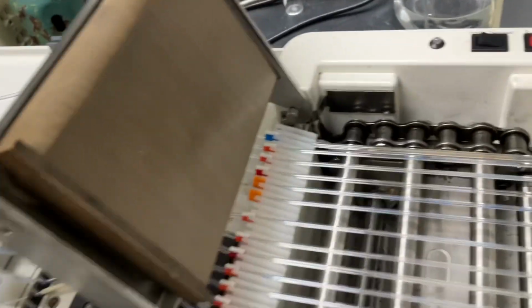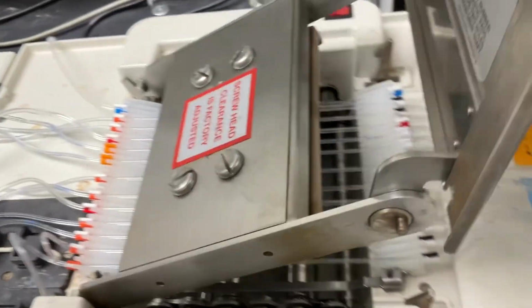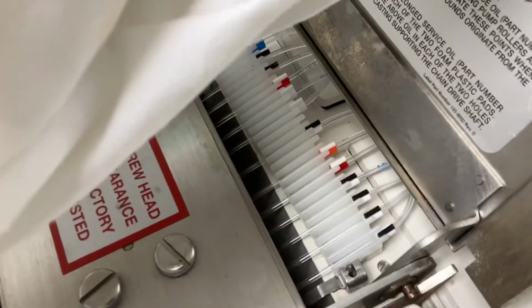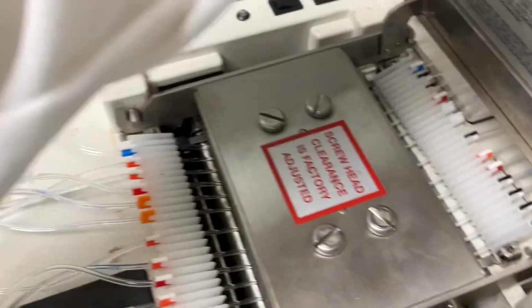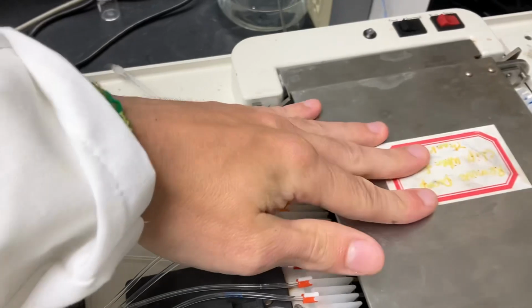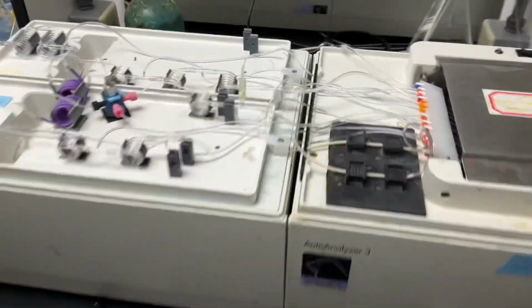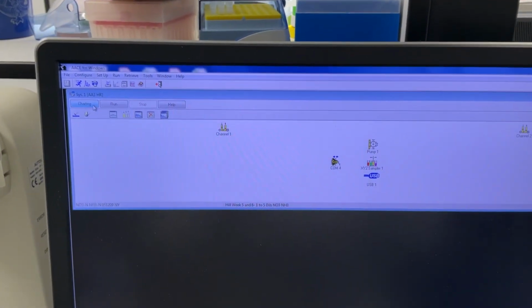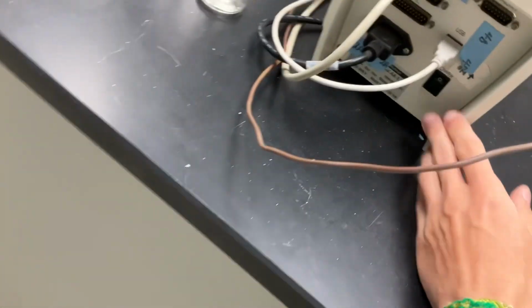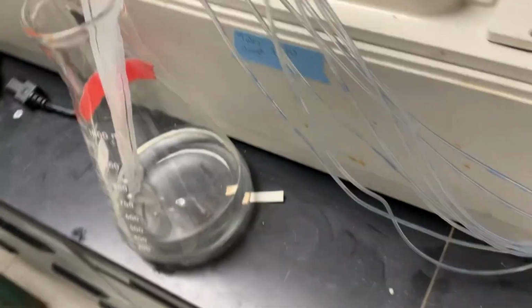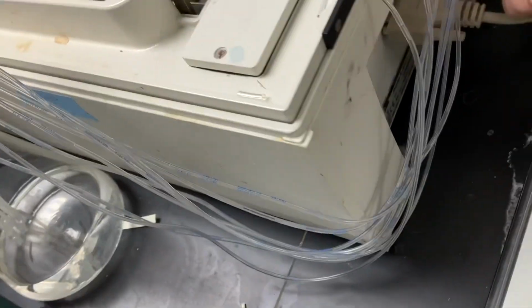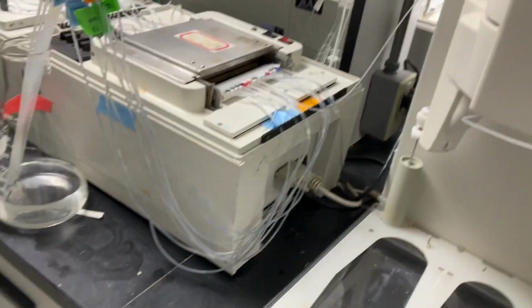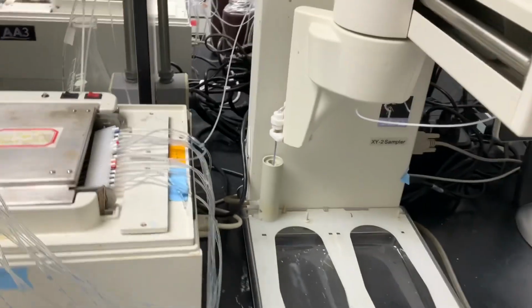So this is me closing the pump right here. You can see by this clamp action, you actually are just sealing those tubes there against a base plate. All right, that's nice and closed. We're good to go. We're going to start the software, and now we're turning on the sensors. We're going to then plug in the water bath. That's the next step right there. I didn't do that because it's not turned on yet. You then turn on the pump housing, and lastly, you're going to turn on this robotic arm.